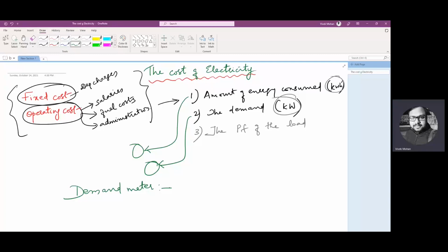So how long should we wait for calculating the average power consumption? What should be the duration considered? This depends on several factors. The period is usually taken to be 10 or 15 or 30 minutes. If the high power lasts for 10, 15 or 30 minutes, and the bill is calculated for every 30 or 15 minutes, then the high power consumption would be accounted for. Normally for large power users like industries or municipalities, the averaging period can be as long as 60 minutes. This is called the demand interval, at which the demand meter calculates the average demand.